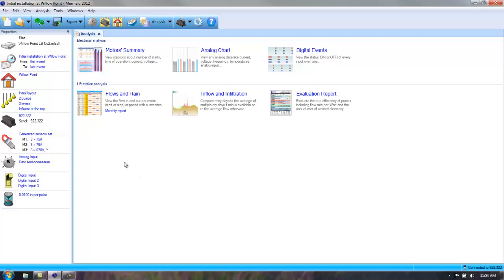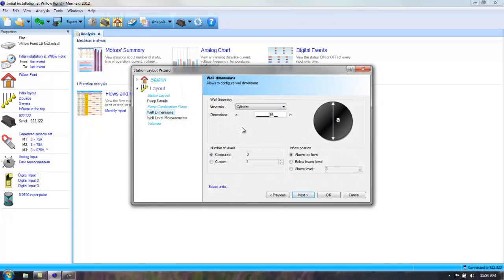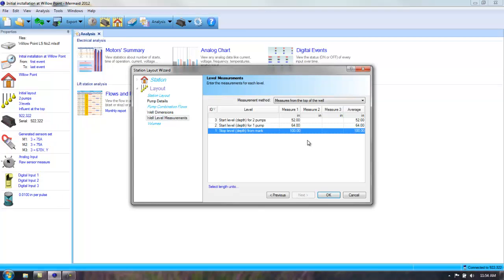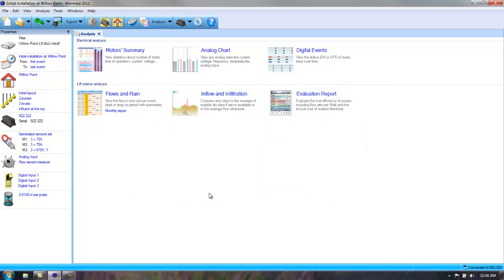So first of all, the levels were incorrect. So I go into this part of the station file. I'll say the cylinder was correct. It wasn't 10 foot, it was 8 foot. But the levels were incorrect. The depth to my all-off was 120 inches. My first on was actually 76 inches. But this time, the lag was 52 inches. So you can modify this after you find out the actual data for that particular station, and then click OK.